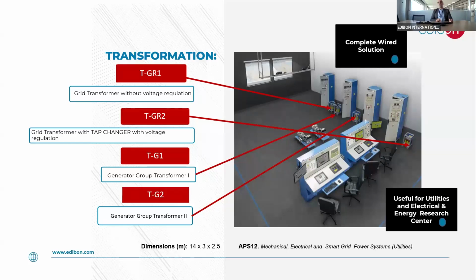Sometimes you can use them to simulate the transformers already inside the power plant that connect the network with the power plant. That's why there's a difference between TGR1 and TGR2: TGR2 includes a tap changer, the other one doesn't. Some transformers include tap changers in order to regulate the output voltage to be adapted with the bus bar. I'm trying to emphasize that these transformers are not similar, and this diversity aims to simulate everything about transformation in the power system.